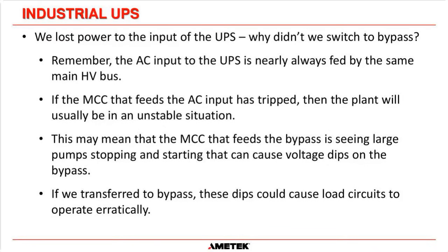Next misconception: we lost power to the input of the UPS. Why didn't we switch to bypass? Now, this is such a common question because a lot of people say, well, if we have bypass, switch to bypass, because therefore we're not cycling our batteries, we're protecting the batteries.